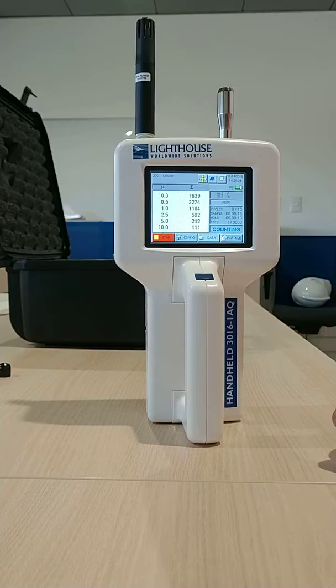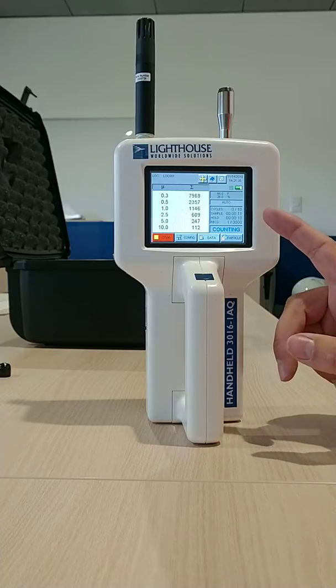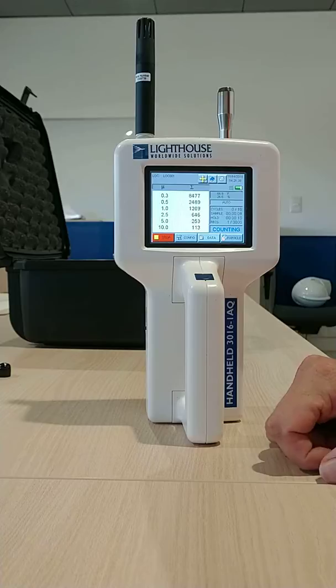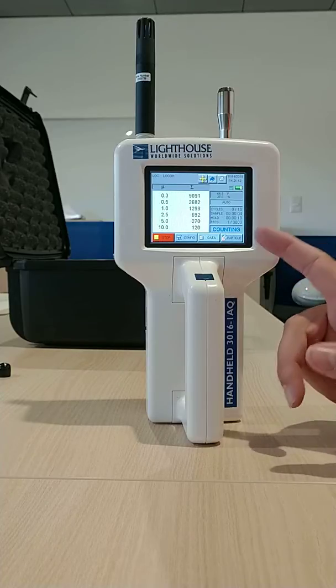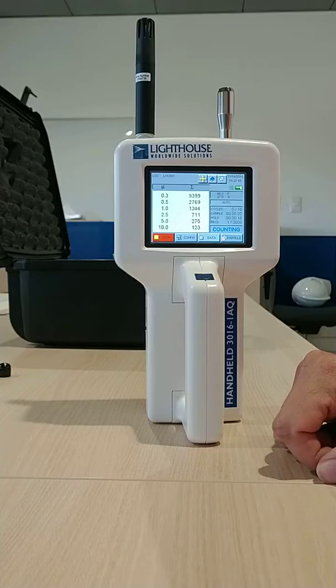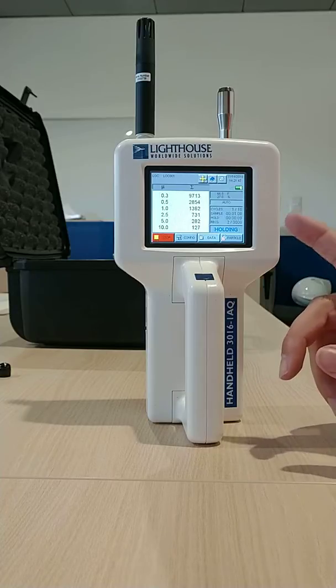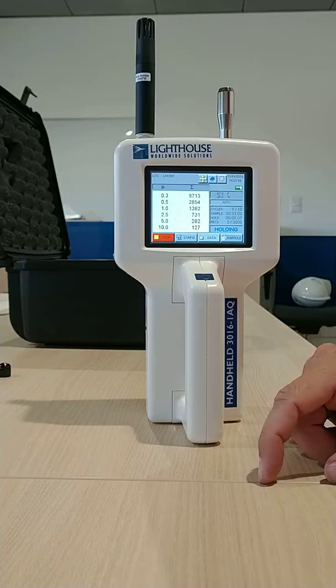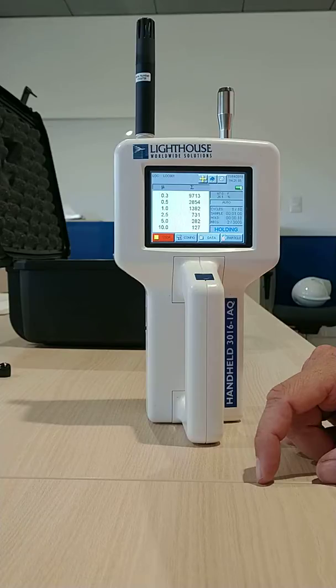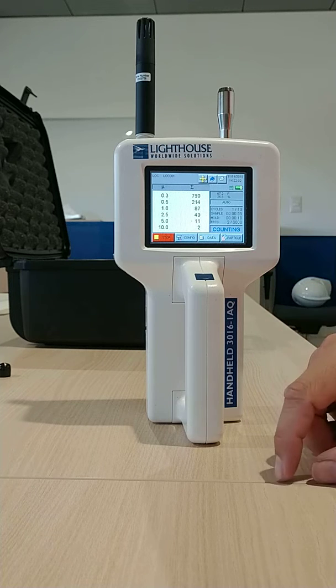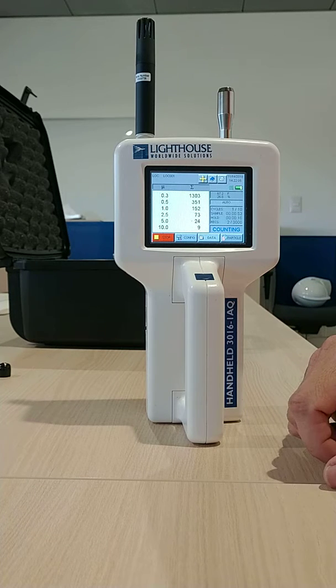It's running off of battery. Right now it's set up to do 10 cycles, each of 1 minute. We're counting down. We've got 7 seconds left. Then it's going to hold. It will store 3,000 particle counts. There are systems in here where it will tell you what your ISO level or your counts per cubic meter are, so you can figure out class 10, class 100, class 1000, etc. But once it's running in a clean room, again, these particle counts should be pretty close to zero.